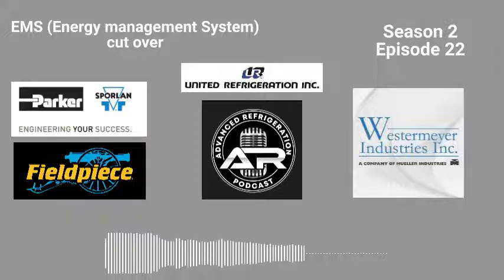I've gotten burned on remote panels in old-school stores that have six or seven remote panels everywhere. A couple of missed boards could really screw your job margins. So I get a solid count of inputs and outputs. Then I'll lay the rack panel out on paper with measurements and see: can I ditch this cable tray to make more room? Do I need to remove boards to the side? I'll lay it out on paper — with measurements, all the boards, how long they'll be, what board goes where. I may take an entire day to do an EMS walk and changeover plan for one store.